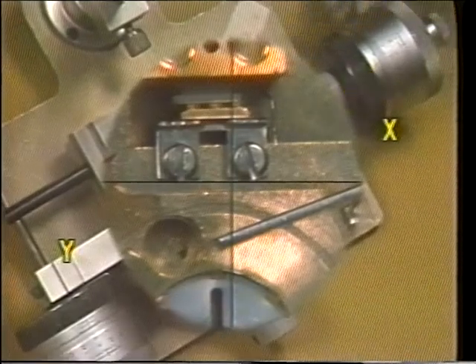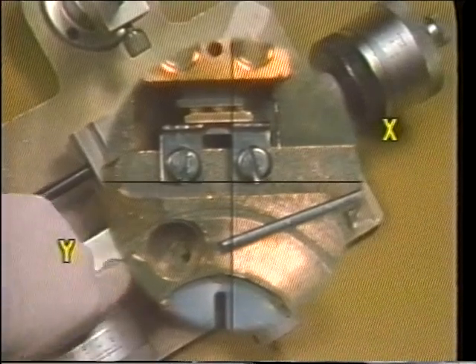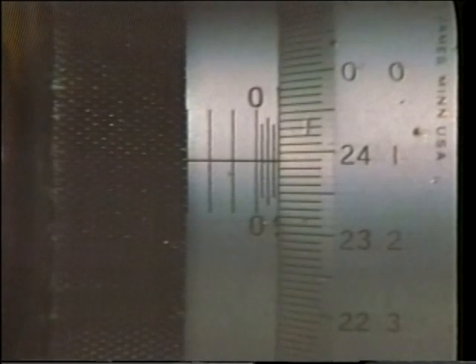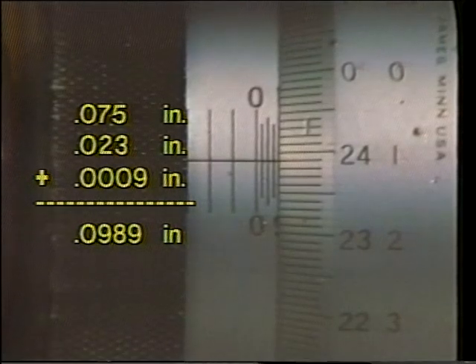Taking a measurement on the x-axis involves the same procedures. After the x-axis micrometer head is set at zero, the operator adjusts the positioning knobs on the micrometer heads until the object is correctly positioned at the zero reference point. Remember that the intersection of the crosshairs — the zero reference point — is the beginning point of measurement. The thimble on the x-axis mic head is turned so that the table moves the object along the x-axis until the crosshairs align with the end of the measurement. The measurement of this dimension is read from the x-axis mic head scales as 98 thousandths and 9 ten-thousandths.